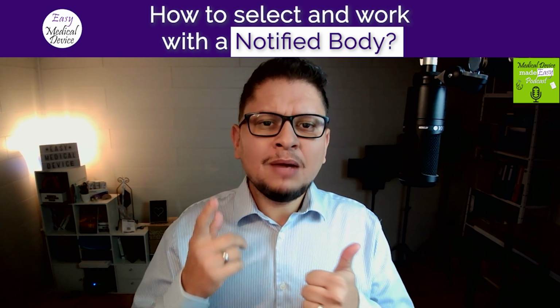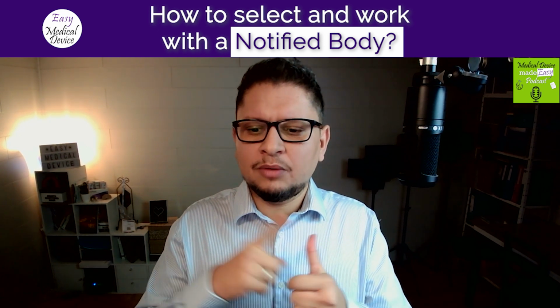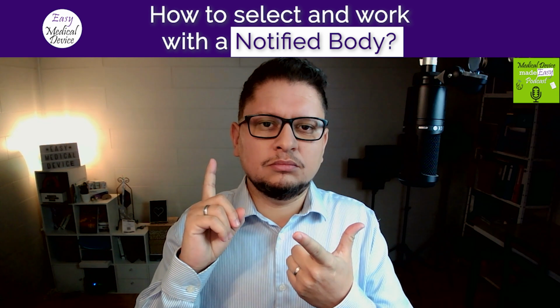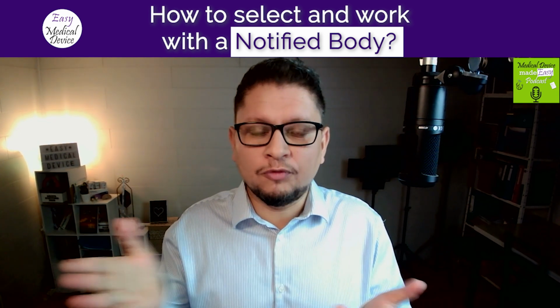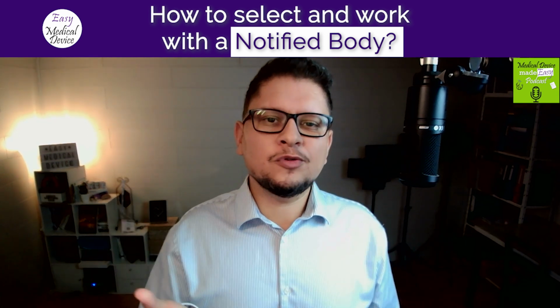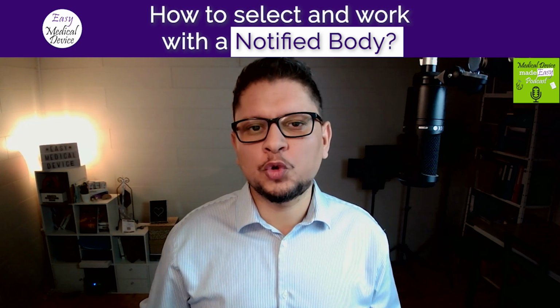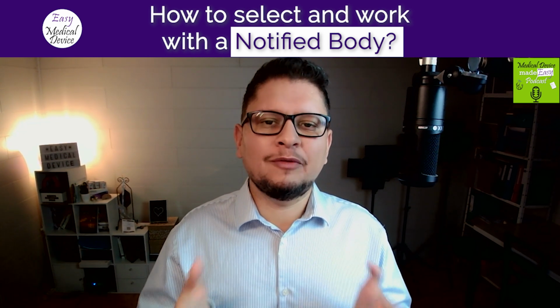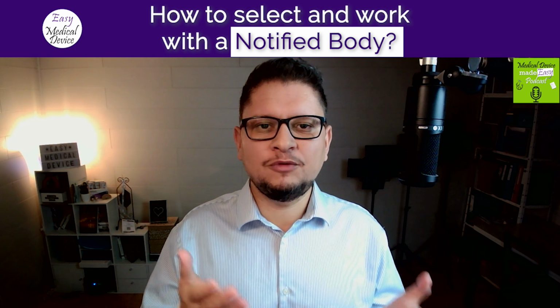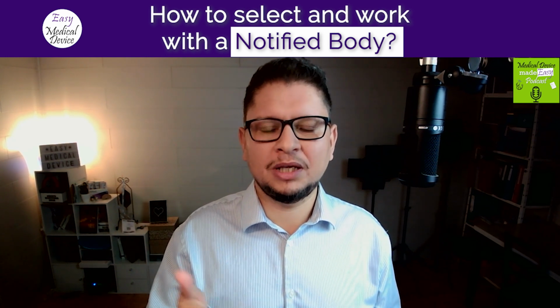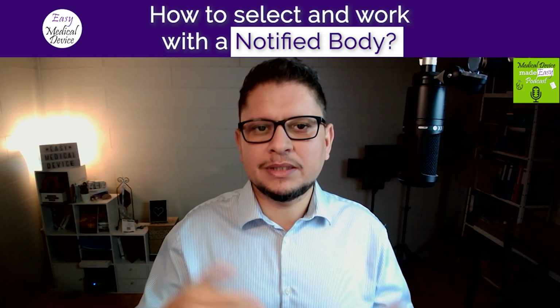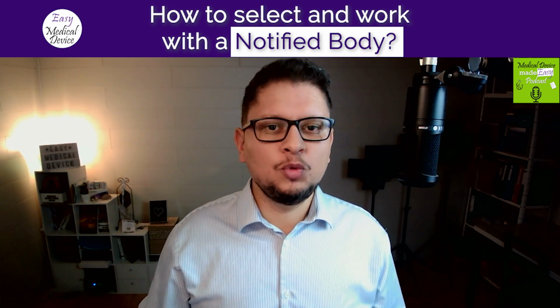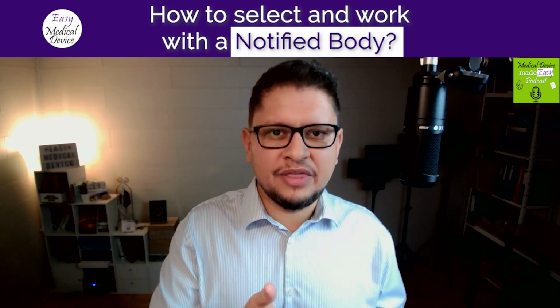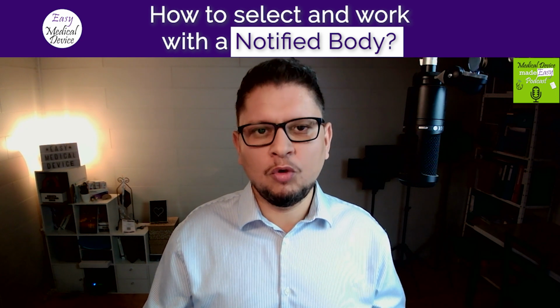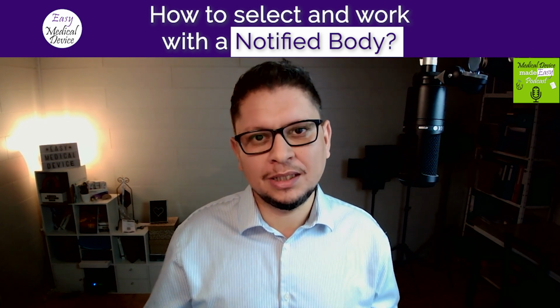So now that you know your MDR code, now that you know your annex, so the route of conformity that you want to go, you have also to define who are your critical suppliers. Here you have really to be careful. What does it mean? It means that if you place a name of a critical supplier in this list, inside the table, this means that you will authorize your notified body to audit them. So it means that you have really to confirm that they are really critical suppliers.